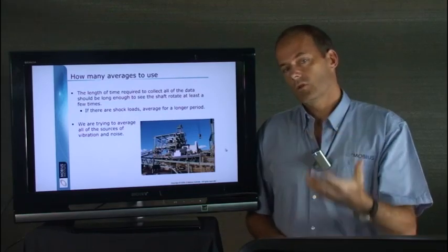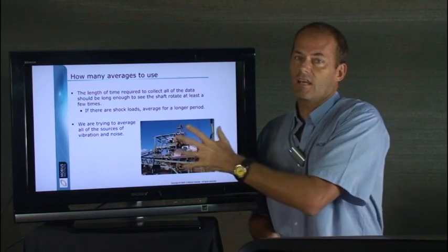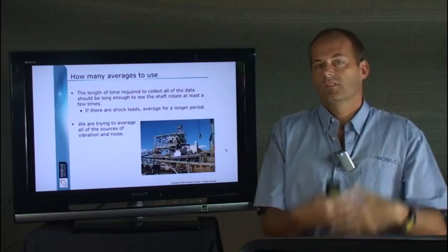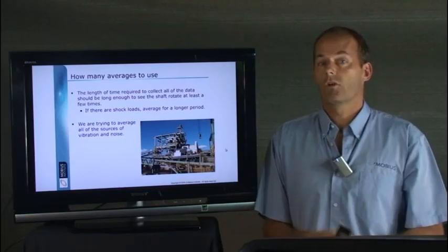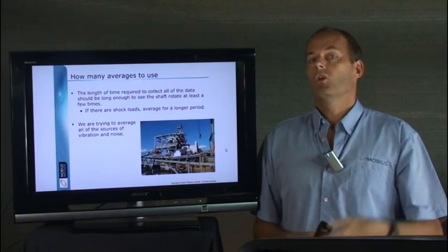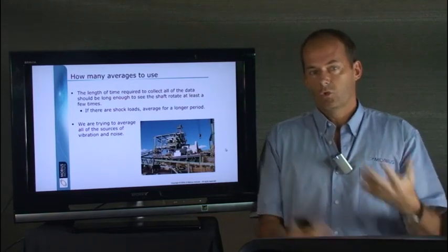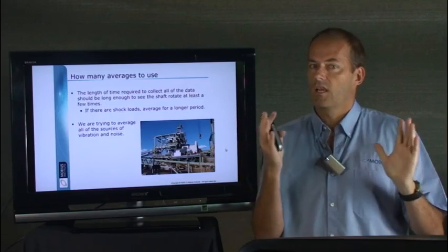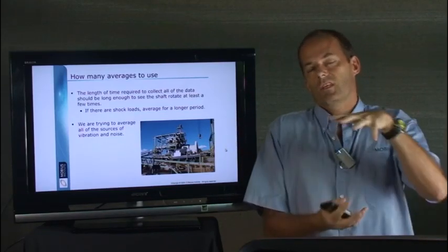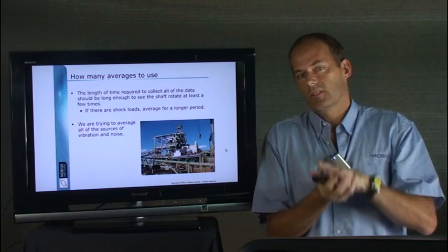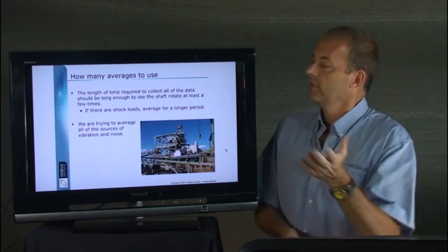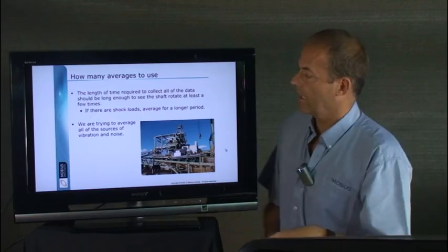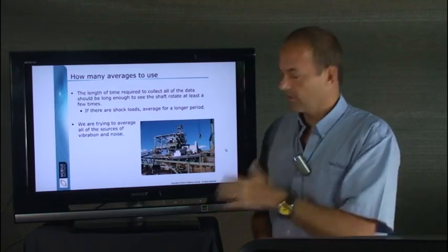You want to listen to it long enough so that the detail you see in the spectrum represents all of the forces and the potential defects that are going on inside the machine. You're also doing it so that all the noise that you normally hear is represented in all of the vibration the analyzer listened to so that we can average the noise together and out of all of this we want a repeatable measurement that we can compare from one moment to the next, but you need to think about the type of machine.